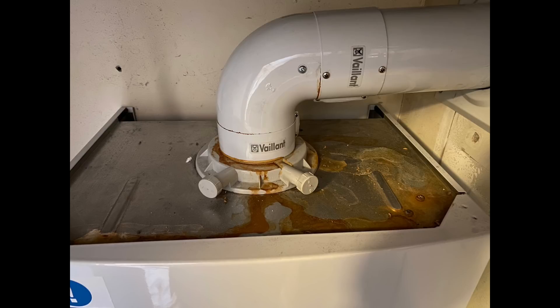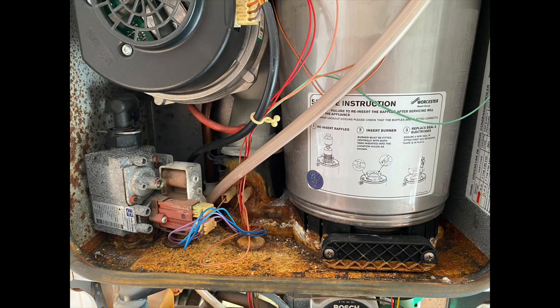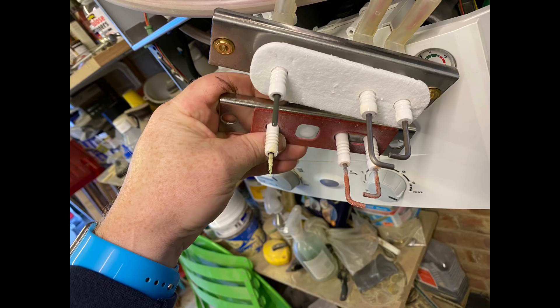I'm not actually sure what this next one is - it's been sent in, so maybe you could add a comment below and let me know what type of flue this is. It looks like it's rotten from the picture. This next boiler is a Worcester Bosch Green Star - I think it's a 24i or 28i Junior - and you can see in there it's obviously been full of water. I would imagine the boiler's been installed on a dirty system or the heat exchanger's gone at some point. It's in a bit of a mess. These are some electrodes out of a Worcester Bosch CDI combi boiler.